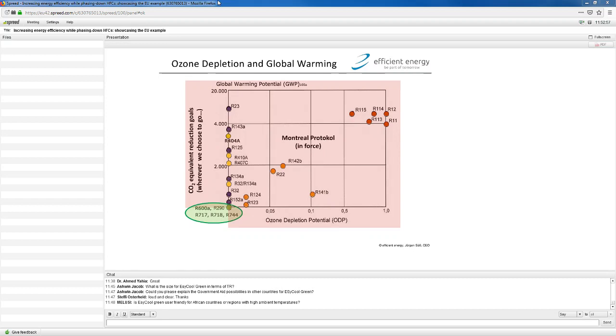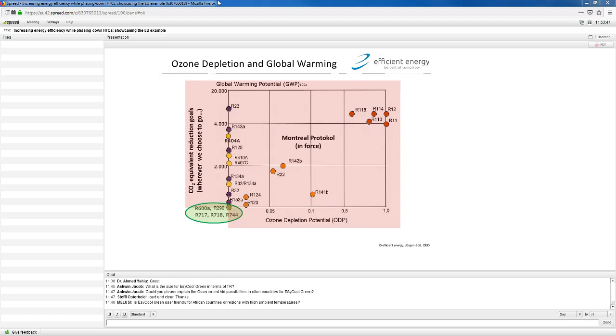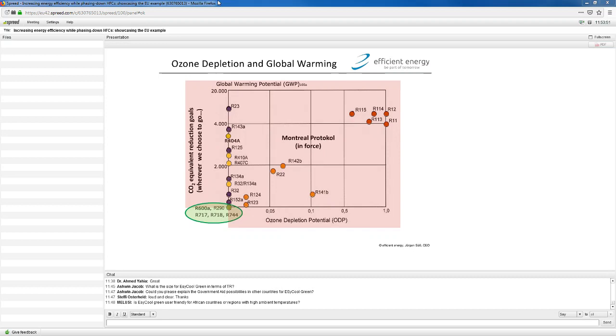The refrigerants that are promoted today—and Daikin just went away from R32, which is pretty far down on this axis—all the other refrigerants on this axis, and this is a chart I made about 20 years ago which is still valid, they will more or less disappear over the years. So you end up with these refrigerants down there in the green bubble where there is isobutane, propane, ammonia, water, and then CO2. This is the refrigerant family that we call the double zero, so it's the ozone depletion potential zero and then also GWP zero. Well, hydrocarbon has got something like three, but it's still okay, I would say.